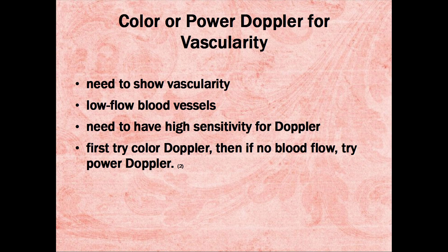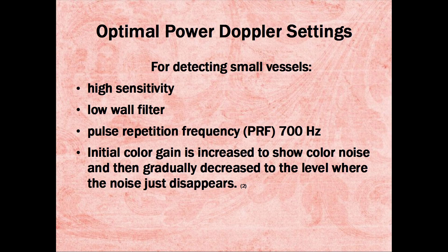We need to use either color or power Doppler to show vascularity. These are low-flow blood vessels going into the lymph nodes, so we need to have high sensitivity for Doppler. First try color Doppler, then if you're not seeing any blood flow, try power Doppler. The settings needed for detecting small vessels are low wall filter, a pulse repetition frequency of about 700 Hz. Initial color gain is increased to show color noise, and then gradually decreased to the level where the noise just disappears.